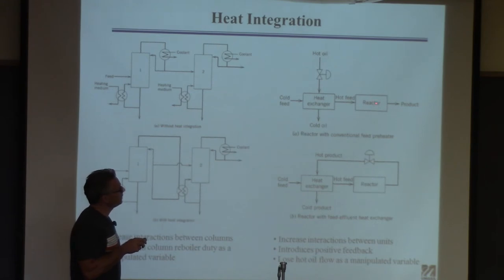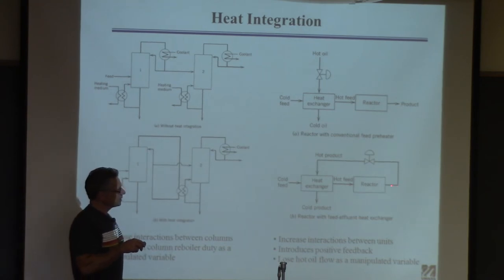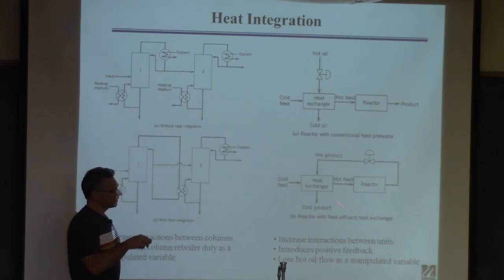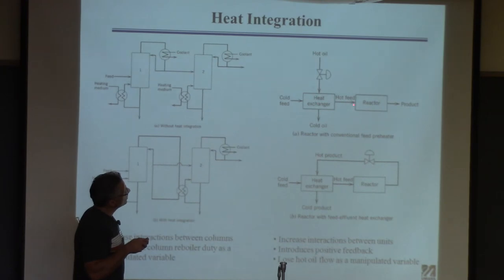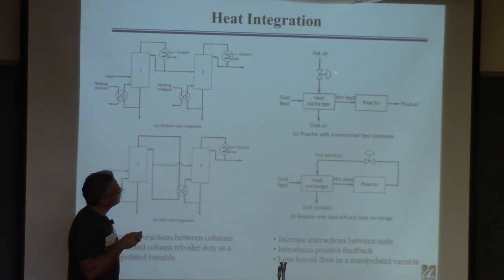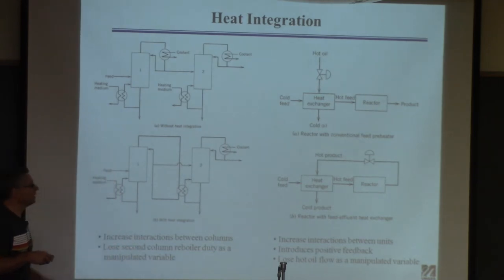There will be more interactions between the reactor and the heat exchanger — in particular, it affects the temperature of the feed. This introduces something called positive feedback. In the world of feedback, we love negative feedback and hate positive feedback. As an example: temperature gets hotter in the reactor, so does the feed, because it heats more here — hotter feed makes the reactor hotter still. You could get into a situation where this thing gets hotter and hotter and hotter, and you lose control of the reactor. That's called positive feedback. Also, we no longer have the heating oil to manipulate — if the reactor got too hot, you could cut back on heating in the heat exchanger to cool the feed and slow the reaction, but now you don't have any control over that.